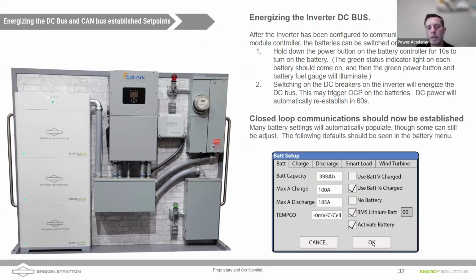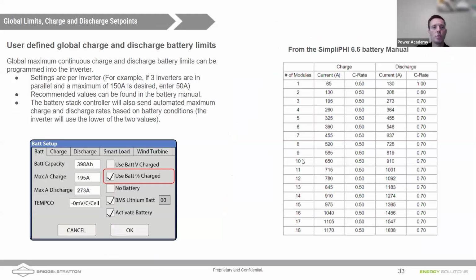Once you've clicked OK to save, as long as your communications are properly there, you should see that battery capacity there. And then the charge and discharge rates you get to set. Those charge and discharge rates are global charge rates. This is DC solar, as well as AC solar, as well as grid. That's the maximum global value, so all charging sources combined. On the charge tab, we will get the option to set that independently.